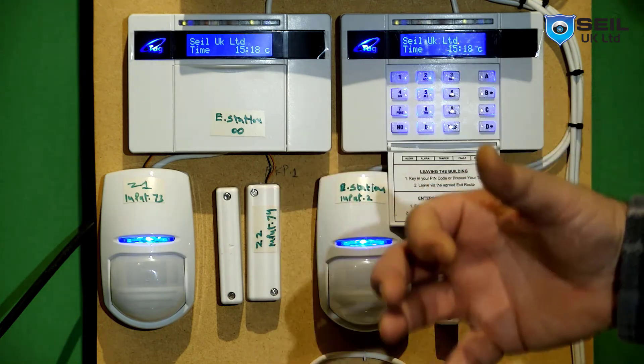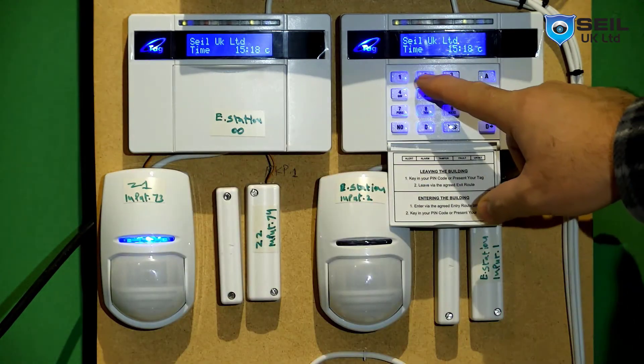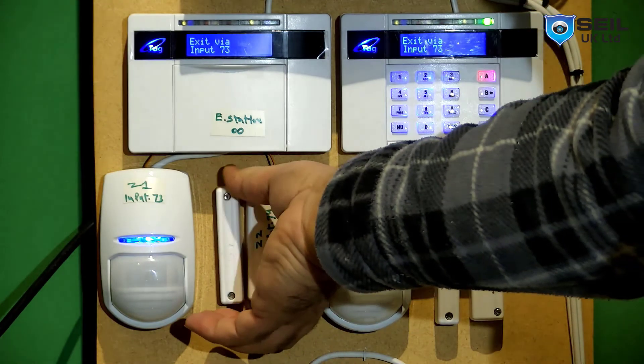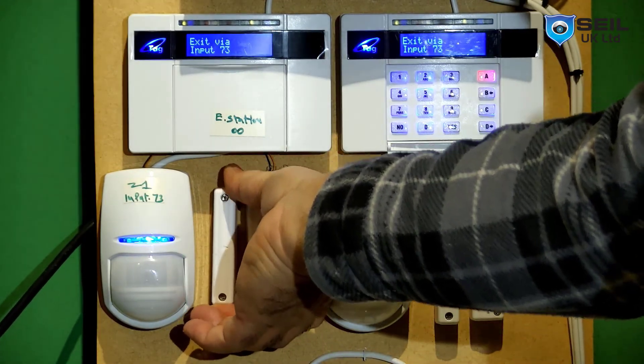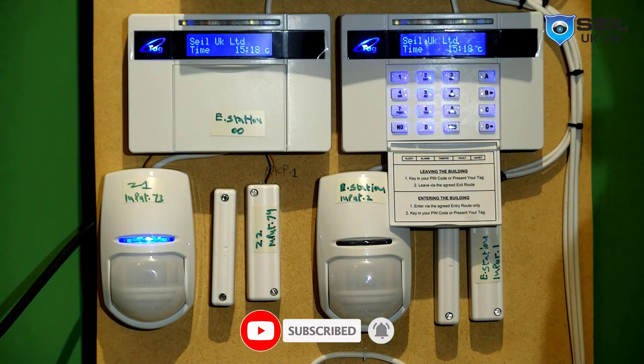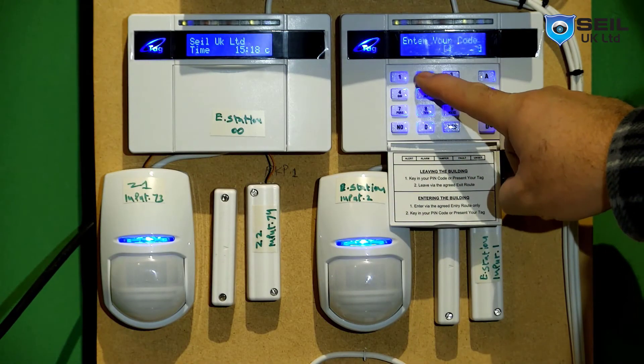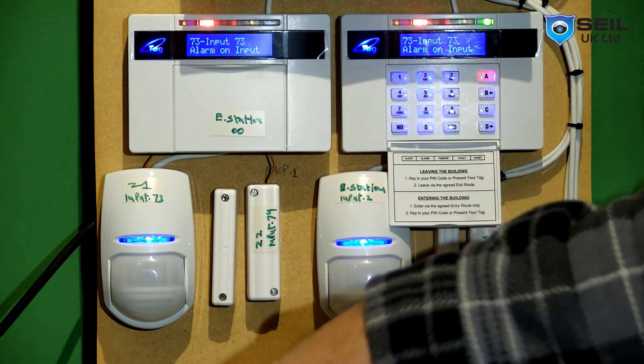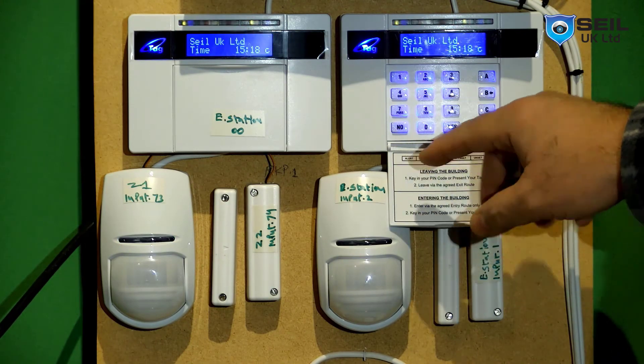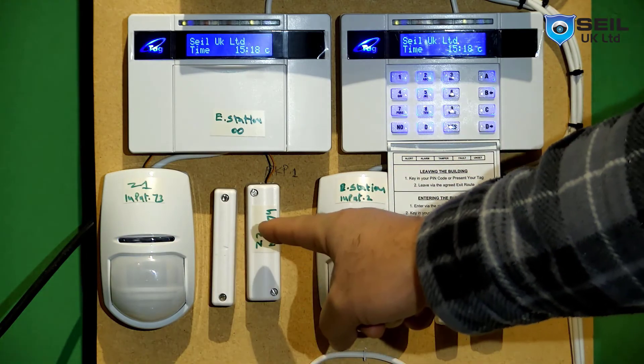Now when we set the full set - A means full set - this sensor should trigger straight away. Let's test it now. Press yes. I exit from the front door and go out, then the door closes. Look - this sensor picked me up straight away. So now it says alarmed input 73, area this area. Press no for reset. So now in part B it is reversed - this sensor gives time and the other sensor triggers straight away.